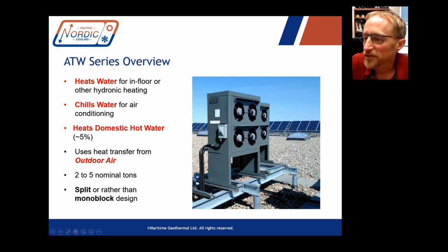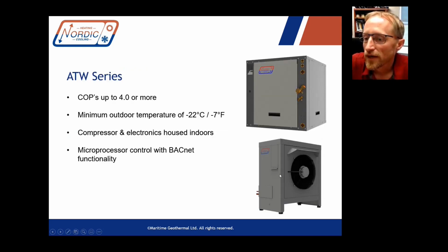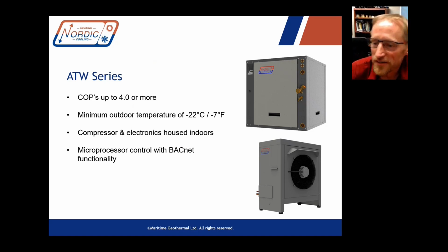All right, so let's take a look at some more slides. Of course, these are just some general points that were in the presentation. COP can be very high, actually, if it's not very cold out, up to 4 or 5, even 6, because it's easy to extract heat from warmer outdoor air in the spring or fall. As I mentioned, the minimum outdoor operating temperature is minus 22 Celsius.